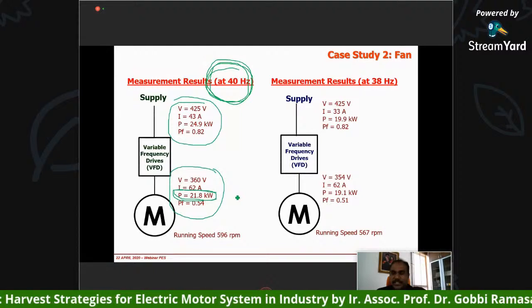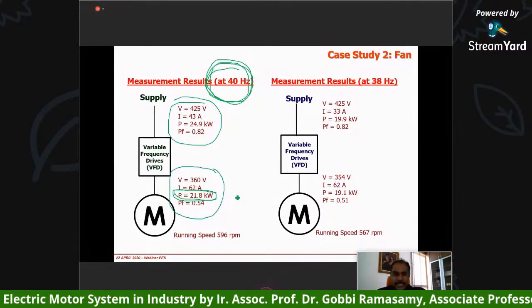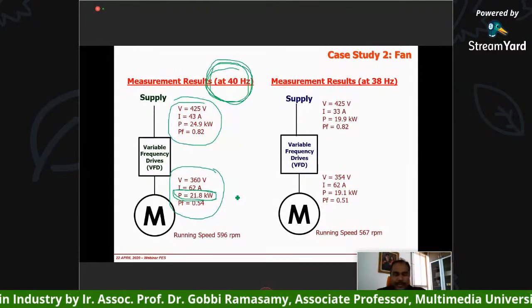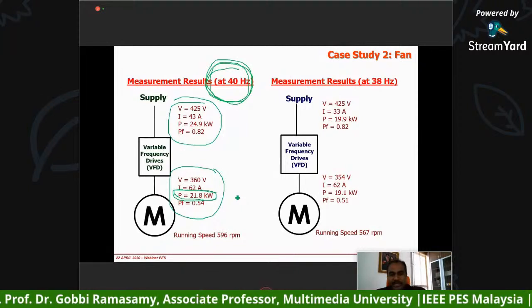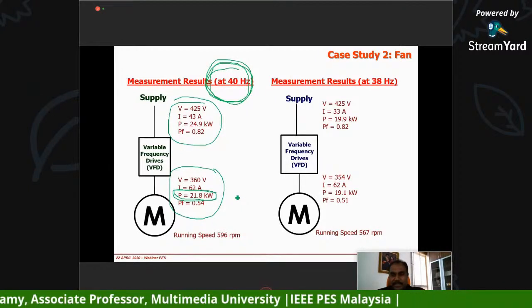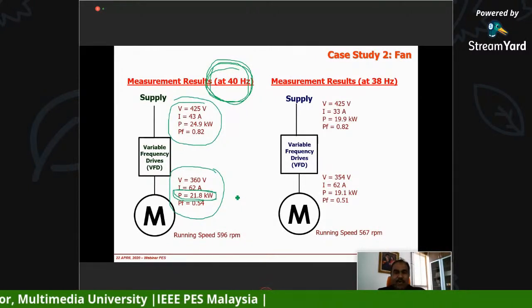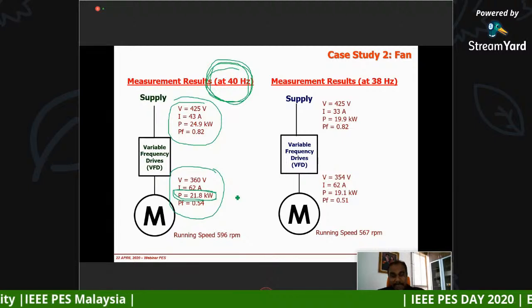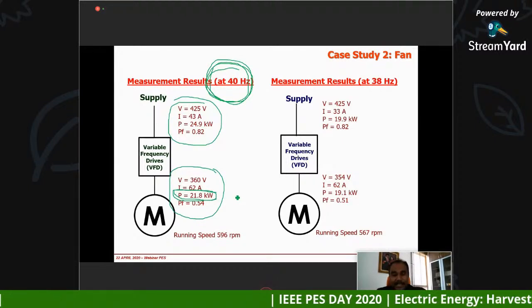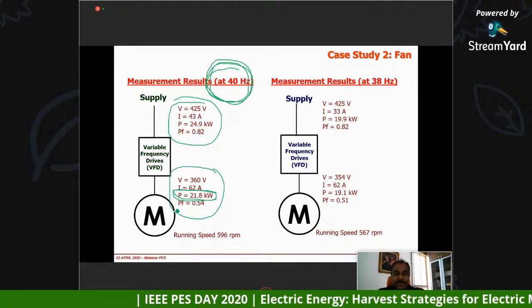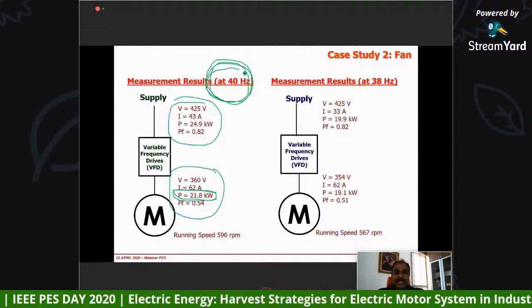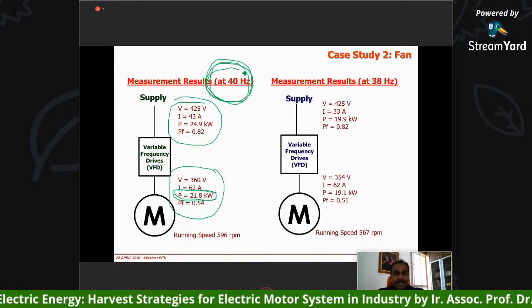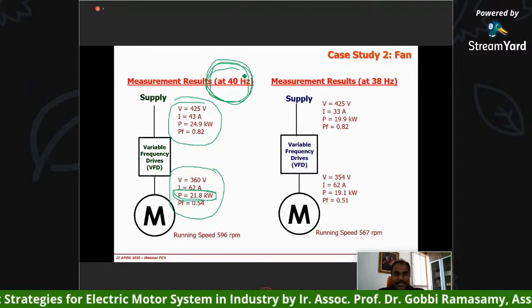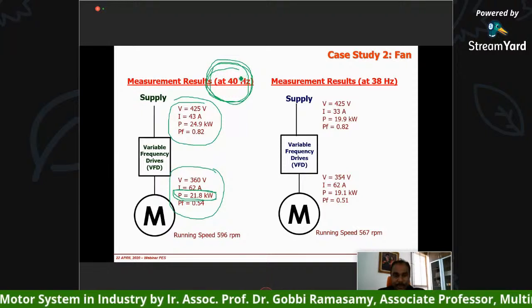That's huge. That means, as I told you just now, this motor is actually driving about 30% loading. That means it's running at a very low efficiency all the time. 120 kilowatt is taking only about 30 kilowatt when it's running at 50 hertz. Okay, that's number one. The motor is oversized. It's running at a light load.